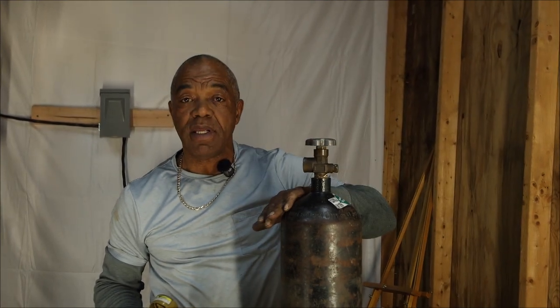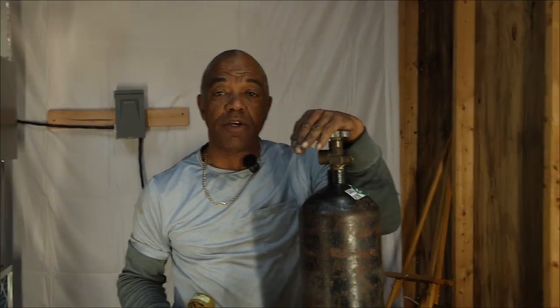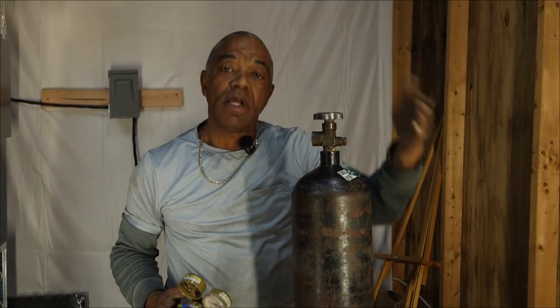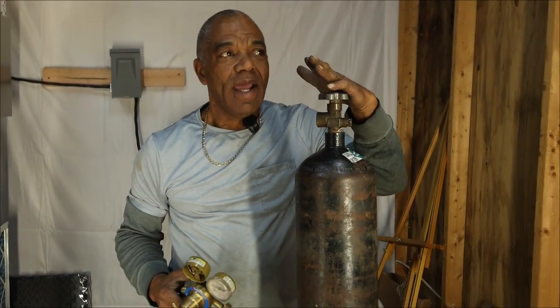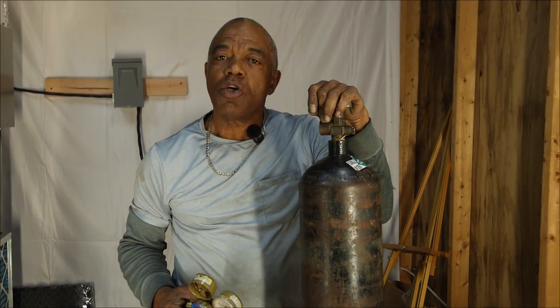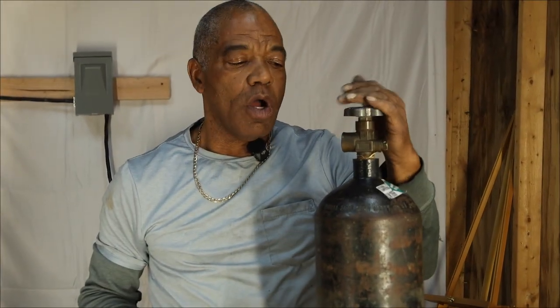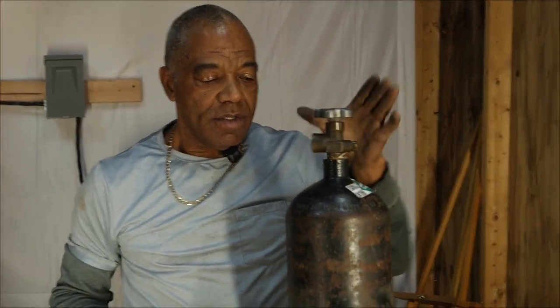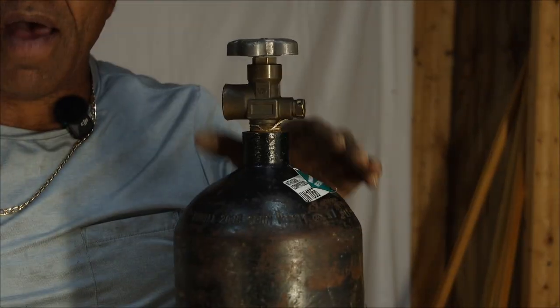When the tank is empty, you take it back to your vendor and trade it in for a full tank. Right now they're charging about $22 for a replacement tank. This comes with 2,500 PSI of nitrogen pressure. I typically use about 300 PSI per installation, so one tank will carry me pretty far, and it only costs $22.